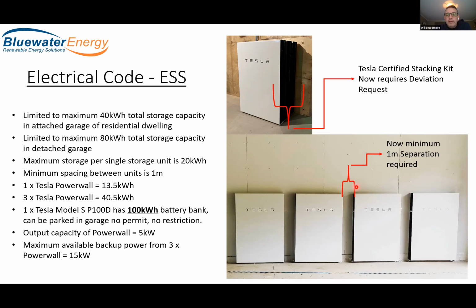Otherwise, what is required is a minimum of 1 meter between units, and I'm using Powerwall as an example here. This applies to all energy storage systems. We need a minimum of 1 meter between batteries, battery cabinets, battery modules, whatever have you. So whereas in the past we were able to place them close together, now these things need to be 3 feet apart at a minimum.